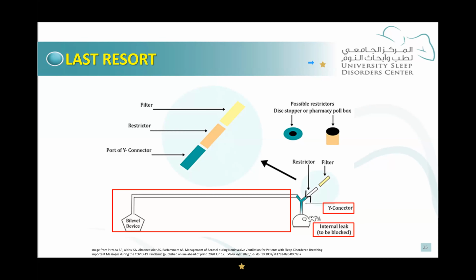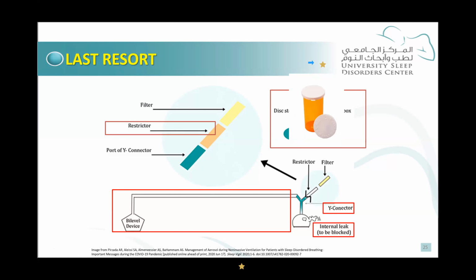And because you're creating now an intentional leak, you have to create something called a restrictor, which does not allow the pressure of ventilation to dissipate through the new intentional leak outflow. You make the restriction by making something like a pillbox, and you make a puncture inside the pillbox with an 18 gauge needle. So this will restrict the flow through the intentional port created by you, then connect it to the filter. So this can be done in an emergency situation where you don't have equipment, so you can create and invent a modified non-invasive ventilation.